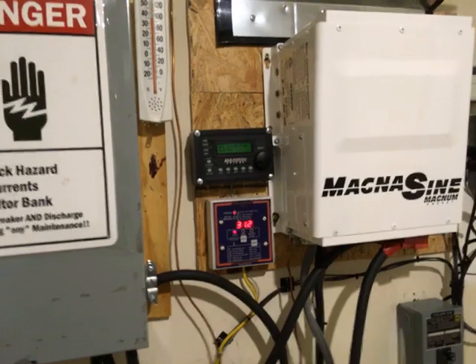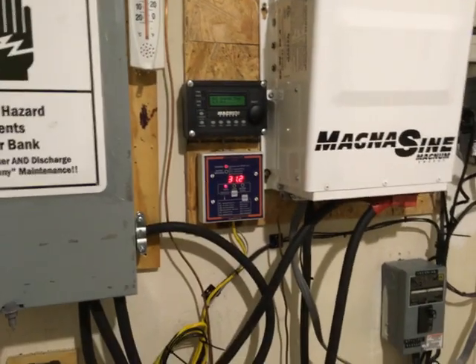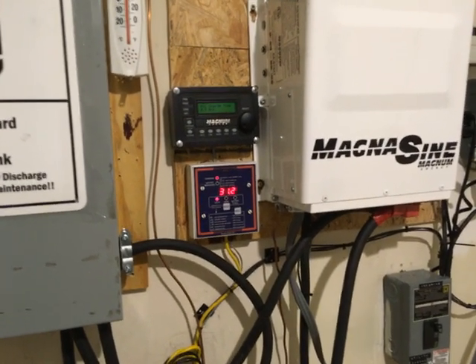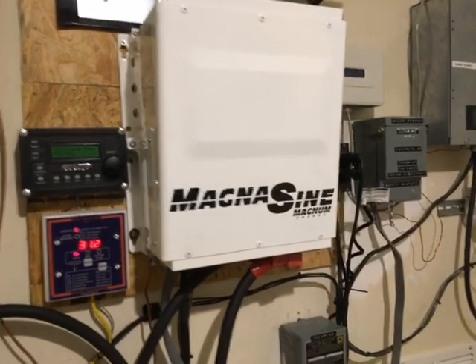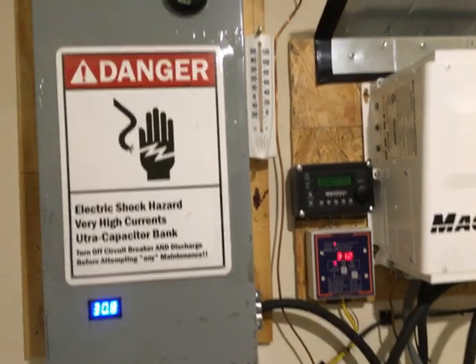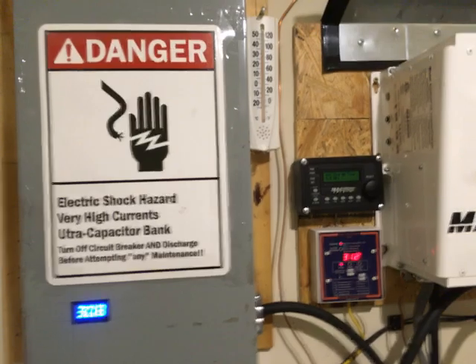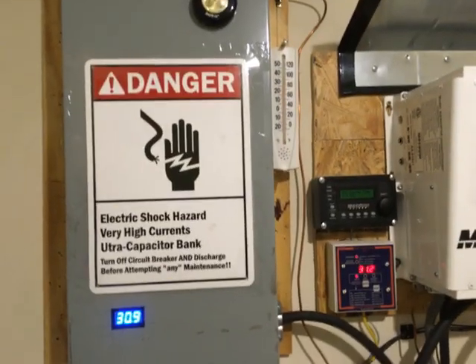When I got up in the morning the battery bank had actually started recharge mode. This is an AC-coupled system, so power was coming in from my grid-tie inverters, being rectified through the MagnaSine, and going to charge the batteries. At that point I simply switched over to grid connection and let the batteries charge normally through the grid.